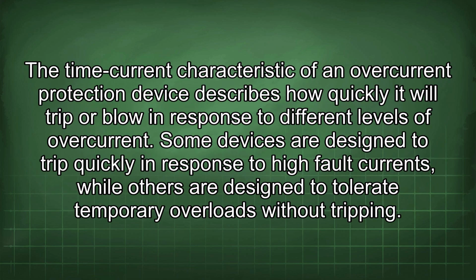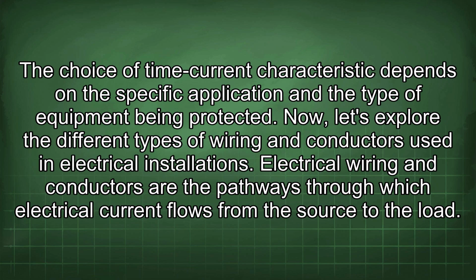The time current characteristic of an overcurrent protection device describes how quickly it will trip or blow in response to different levels of overcurrent. Some devices are designed to trip quickly in response to high fault currents, while others are designed to tolerate temporary overloads without tripping. The choice of time current characteristic depends on the specific application and the type of equipment being protected.